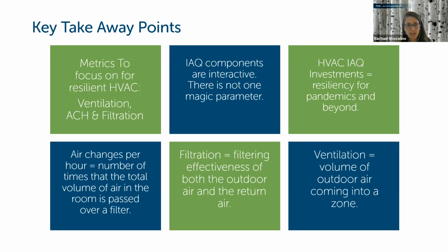I have customers who really want to key in on CO2 levels. They want to key in on the MERV rating of their filters, but they aren't really interested in paying attention to the number of air changes, so the number of times that the air is passing over the filters. It's all of that together. And again, this is not about guaranteeing that anyone is going to be exactly safe. It's about how this HVAC system and the indoor air quality plays into your risk mitigation strategy, which plays into the resiliency and the ability of your building to stay occupied during a variety of outside influencing conditions.